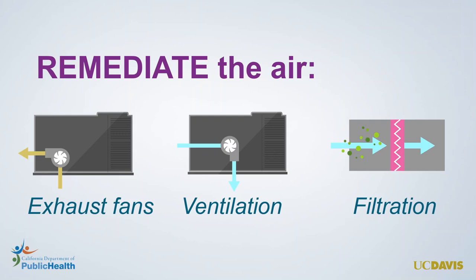Ventilation is the main strategy used for removing indoor pollutants that are gases. For removing particulate matter, including those that contain virus and bacteria, we can also use filtration. With filtration, we send air through filters, and the small fibers of the filters trap particles and remove them from the air so that the air coming out the other side of the filter is cleaner. A great way to increase remediation of our indoor air is to upgrade the HVAC filters. We can also place portable air cleaners directly inside a room to remove even more particles, which can be beneficial during high pollution events like wildfires or when we're particularly concerned about disease transmission, such as flu and cold season.